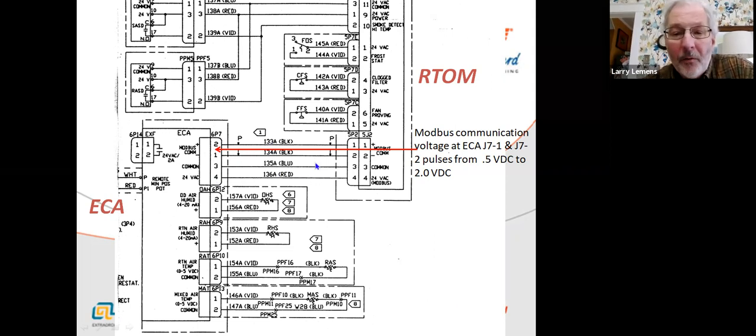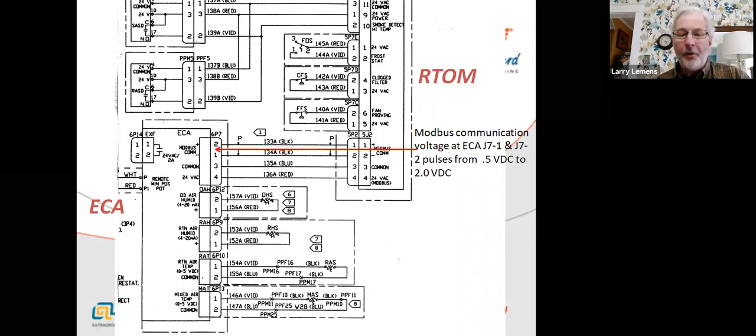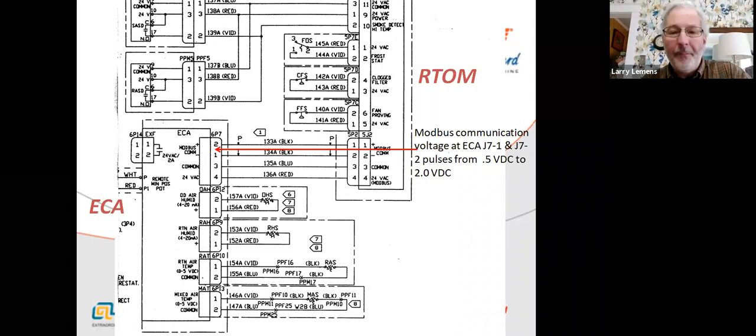Difference is Reliatel has 4 pins, and the old microcontrol has like a 16-pin connector up near the roof of the unit. But it does the same thing. If you turn the power off, unplug it, turn the power back on, it will reactivate as if the economizer was never there. So, again, simple troubleshooting things.